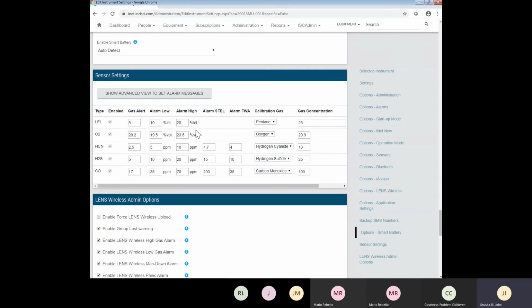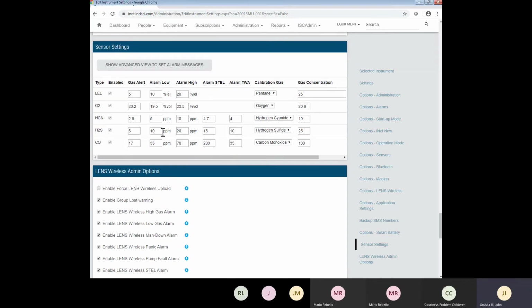Now, with the sensor settings, this is what I was talking about with the alarm TWAs and the STELs. And if you're not going to use TWAs and STELs, what you're going to want to do is crank these numbers as high as they'll go to keep it from ever actually getting into the STEL or the TWA. So you would just come in here and change that value all the way up. Okay. Same thing with all of your normal gas settings.